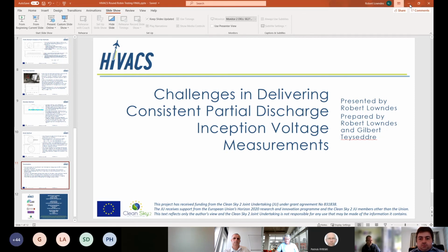So there's a question from Jasper. He's asking, what is the impact of the tightness of the wire around the mandrel? So this is something that we've not formally tested within the laboratory, but from a purely clearance point of view, you would expect some increase in the PDIV because you've got that extra bit of insulation from the air in the clearance between the wire and the mandrel.